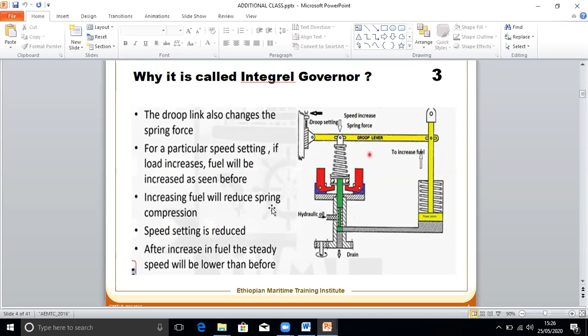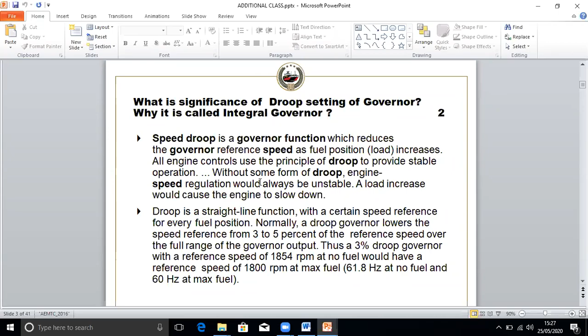What is the function of the speeder ring, flyweights, power piston, hydraulic pilot valve, etc. So speed droop means it's a governor function which will reduce the governor reference speed as the fuel position increases. And all engine controls use the principle of droop to provide stable operation. Without some form of droop, engine speed regulation is unstable. A load increase would cause the engine to slow down. When you increase the load, what happens, why the speed is reduced, that you must understand.